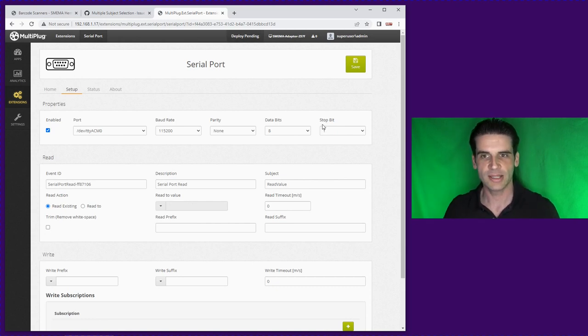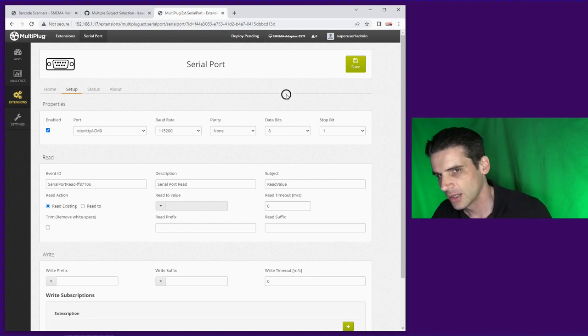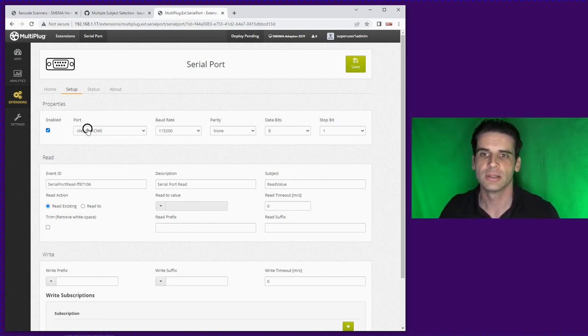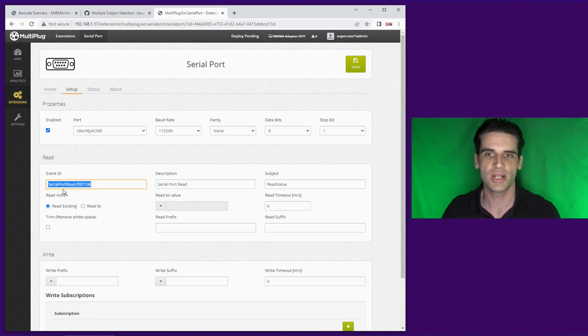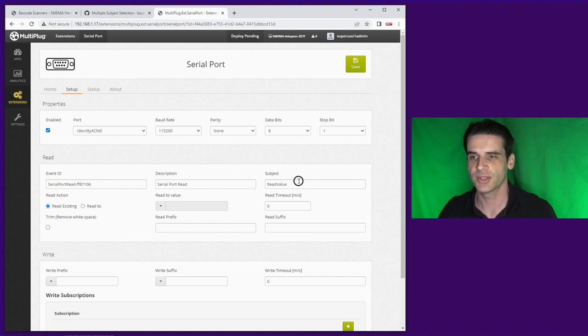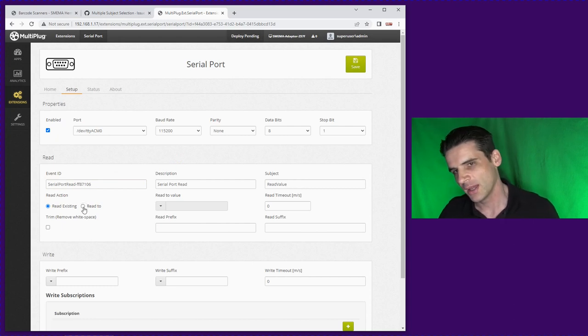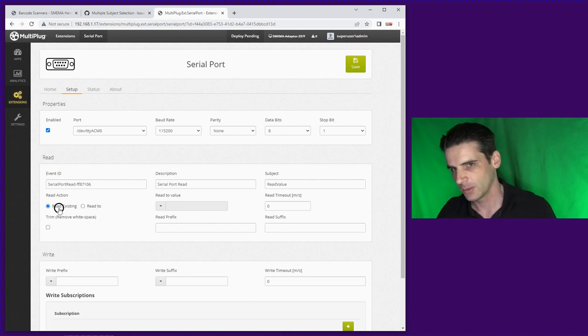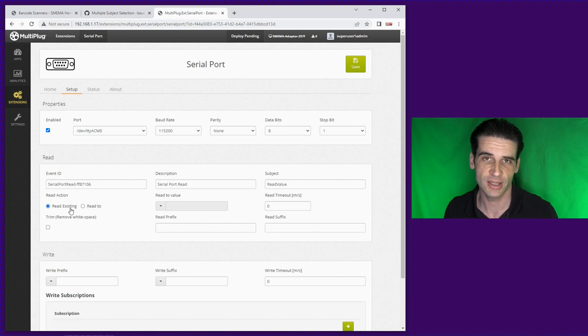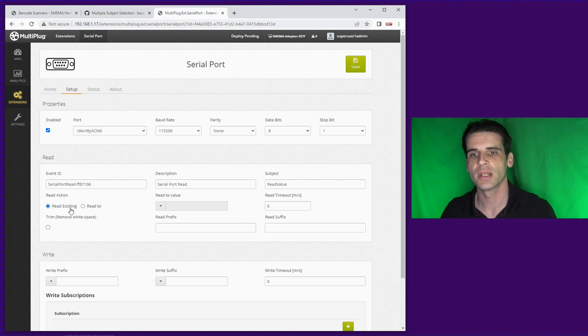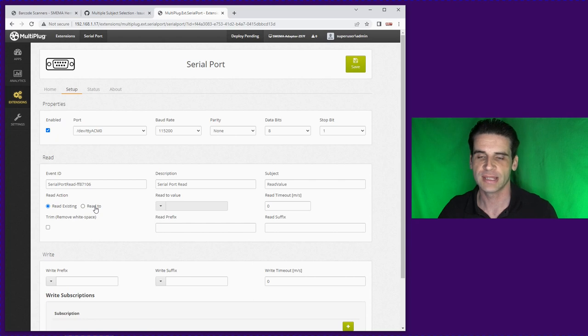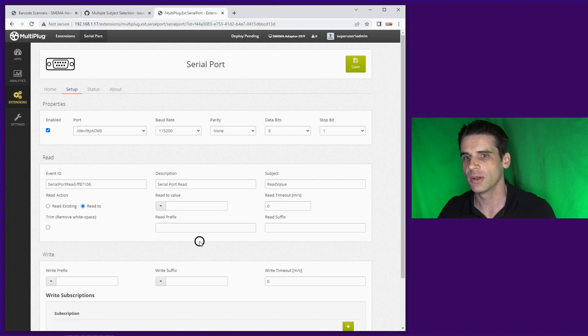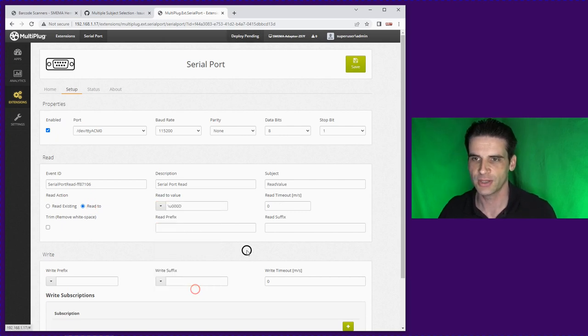We can then enable it making sure the values are correct which they will be. When the barcode gets read it creates an event, so this is a read event. This is where the termination character comes in. We can read to existing which basically tries to read all the data inside the buffer or we can do it to the end of the character. This is the more safe way of doing it.